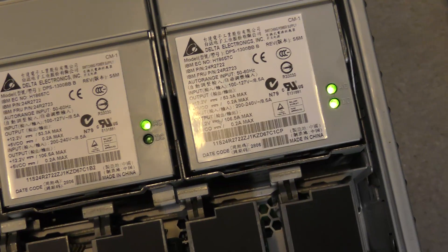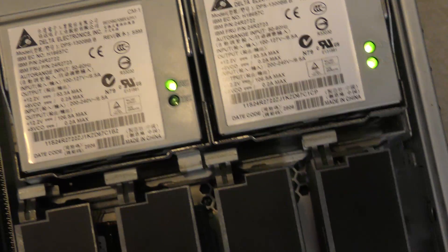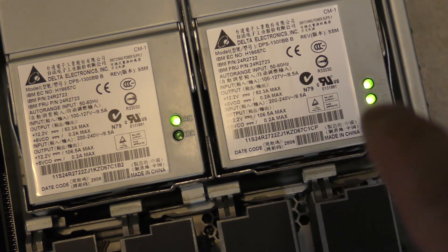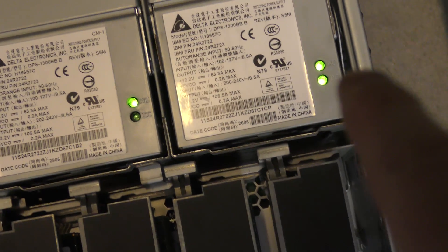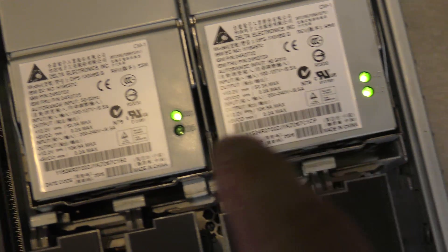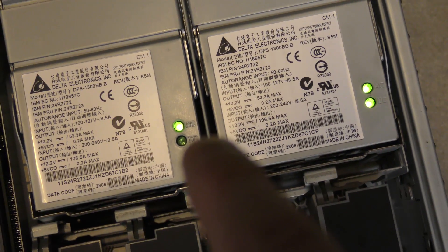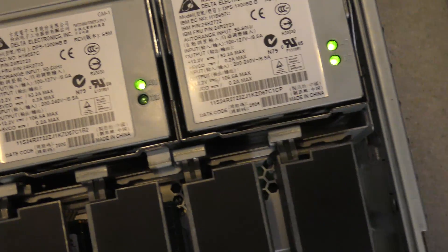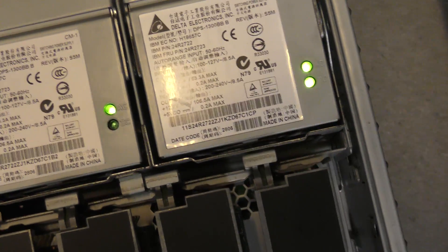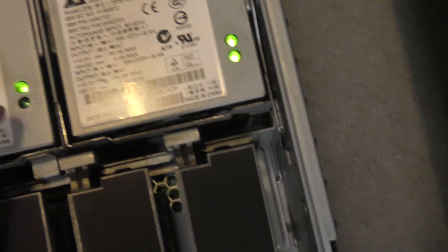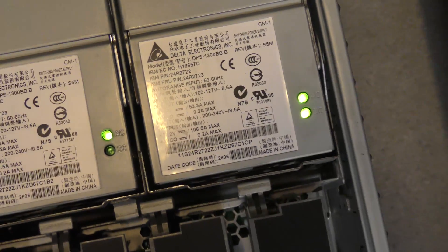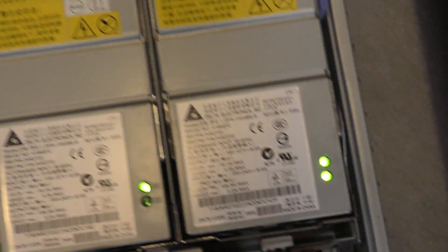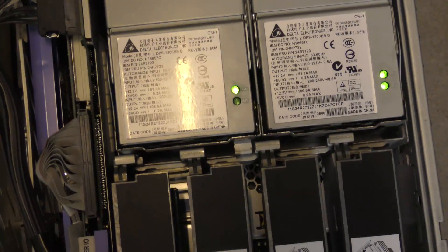There is actually a couple of LEDs on the power supply here. This one seems to be good at AC and DC. And over here, this one says that it's only green on AC and the DC is not green. So this becomes easier and easier. That's the faulty one.